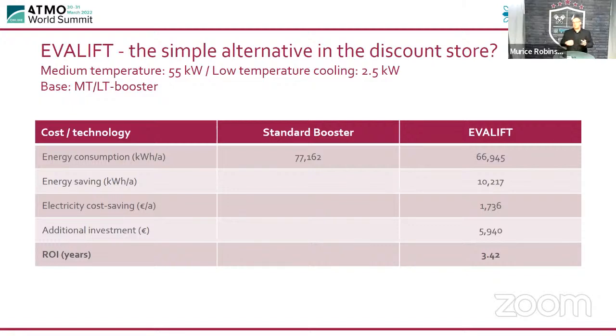However, the low temperature is obviously not going to give you that much saving because you've only got 2.5 kilowatts. But the saving in kilowatt hours per annum was 10,000. So if we convert that into euros, we're saving 1,736 euros. The additional investment for the EVALIFT, like I said, with the plate heat exchangers, the controls, and the three-way valve, only takes 3.5 years to pay that system off. And just remember, that's a small system.